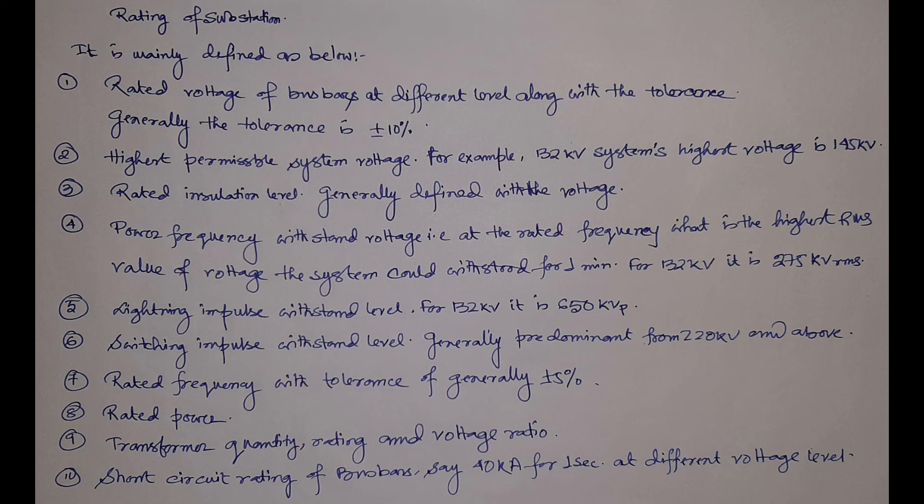Then comes the rated frequency with tolerance — frequency tolerance is ±5%. In many countries the rated frequency is 50 Hz and in others it is 60 Hz. Then the rated power — how much power the substation is handling — which is basically the rating of the main power transformer. Then comes the transformer quantity, rating, and voltage ratio — you must mention how many transformers will be used, their ratings, and voltage ratios.